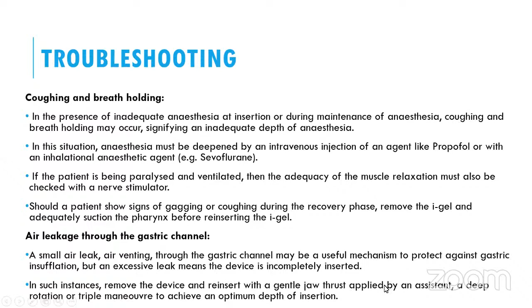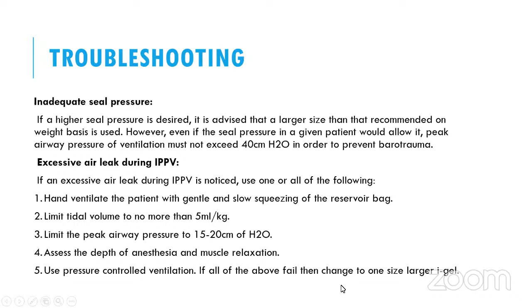Inadequate seal pressure: the seal pressure must not exceed 40 centimeters of water, and a larger size than that recommended on a weight basis is advised if we require a higher seal pressure. When there is excessive air leak during intermittent positive pressure ventilation, hand ventilate the patient with gentle and slow squeezing of the reservoir bag, limit tidal volume to no more than 5 ml per kg, and limit the peak airway pressure to 15 to 20 centimeters of water. Assess the depth of anesthesia and muscle relaxation. Use pressure controlled ventilation. If all the above fail, then change to one size larger i-gel.